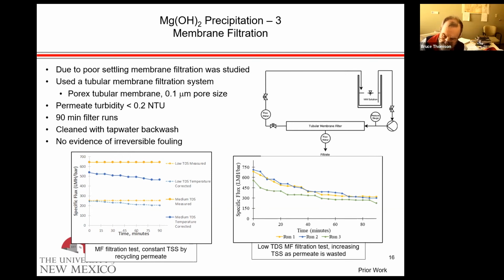The other thing regarding fouling, for inland waters, the principal fouling minerals are limestone, calcium carbonate, calcite, aragonite, whatever you want to call it. And by removing all the dissolved CO2, we eliminated the potential for calcium carbonate fouling. And the other one, out here in New Mexico, a lot of our waters have very high silica, particularly the deep ones. The solubility for silica is somewhere around 120 milligrams per liter. It depends on a bunch of parameters, but 100, 120. Many of the typical wells, the well that Charlie was working on out there in Sandoval County, were already at the saturation level for silica.